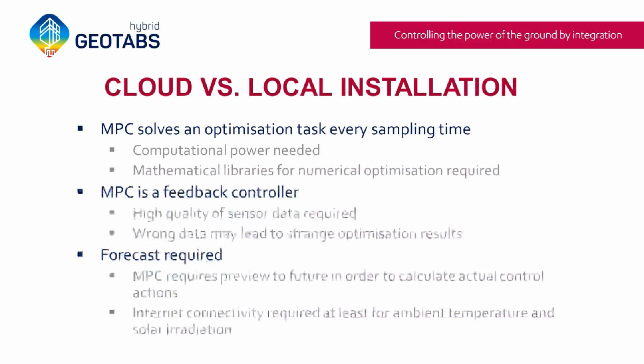The second point is that MPC is a feedback controller, and as a feedback controller it needs data fed into it, and it's really important to have high quality data, because poor quality may lead to strange results. For example, if there's a sensor fault so the temperature isn't 23 degrees but a frozen value that stays the same, and MPC takes this value and makes decisions based on it, that's a wrong decision at the end. Normally buildings are controlled using heating or cooling curves, where this kind of data isn't used directly in the control loop. So basically there's a premium on high quality data.